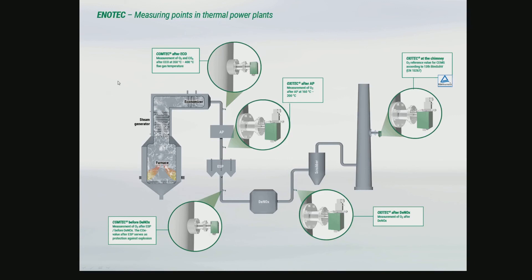So what are typical installation points for the Comtec system? In this power plant illustration, the first measuring point would be after the economizer, before the air preheater, for combustion control. The Comtec analyzer is used to optimize combustion and reduce harmful emissions. After the electrostatic precipitator, or ESP, the Comtec analyzer is used as a shut-off switch for safety monitoring and explosion protection. Generally, Comtec can be used in many combustion applications for process control or as a safety measurement.